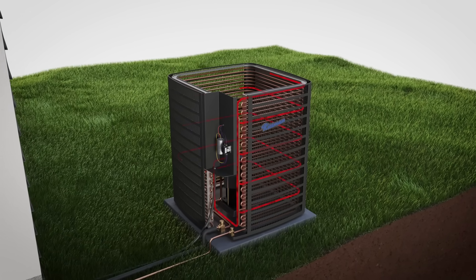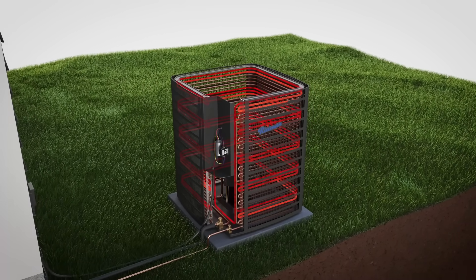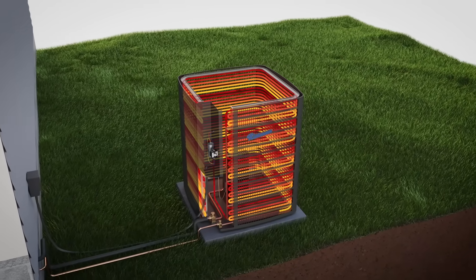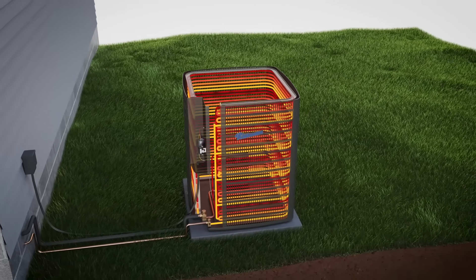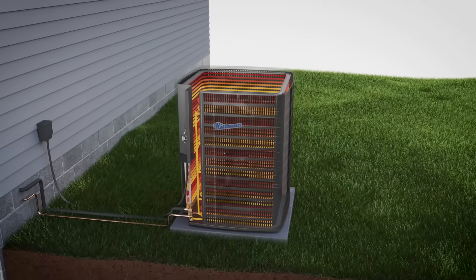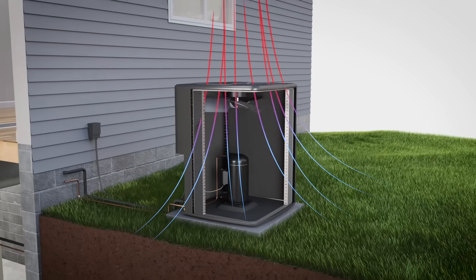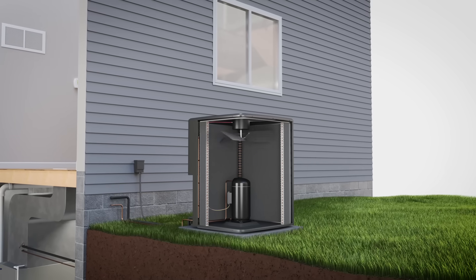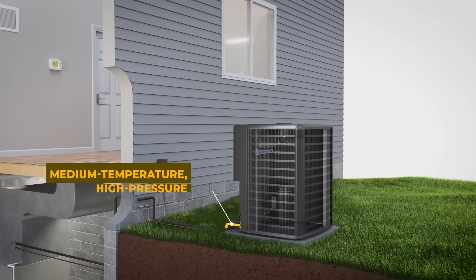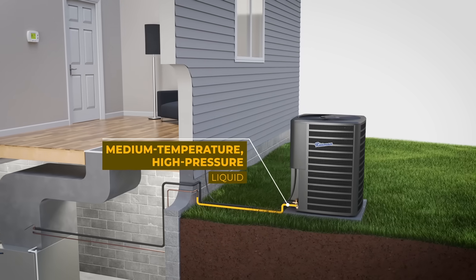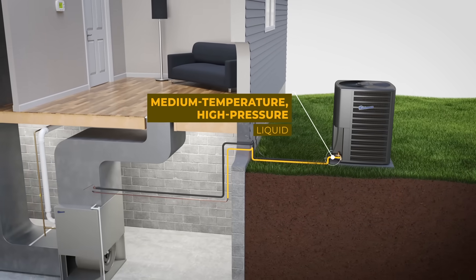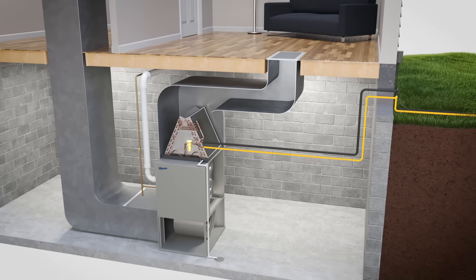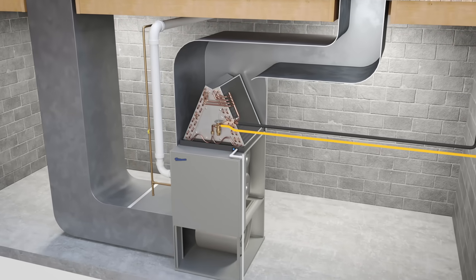After it's compressed, the refrigerant leaves as a high temperature, high pressure vapor. It then travels through the condenser coil where the vapor condenses into a liquid. The heat it has collected indoors and after compression is released outside — the fan inside the unit helps with this process. The refrigerant leaves the condenser as a medium temperature, high pressure liquid.